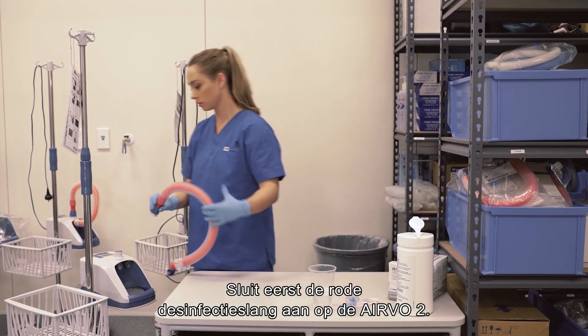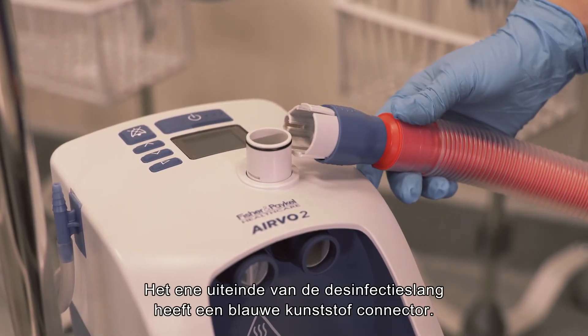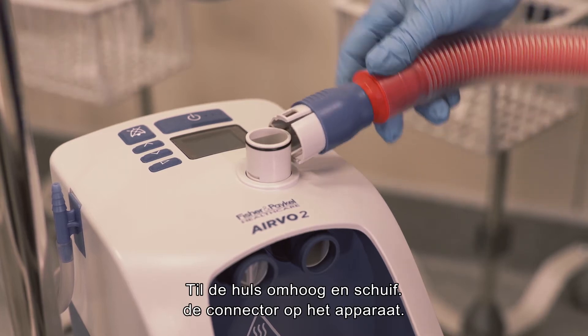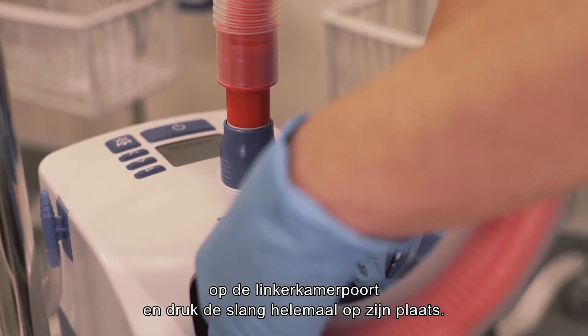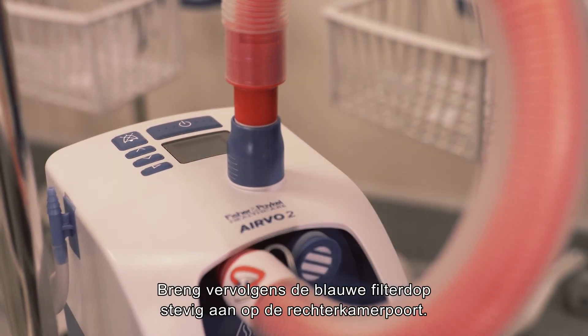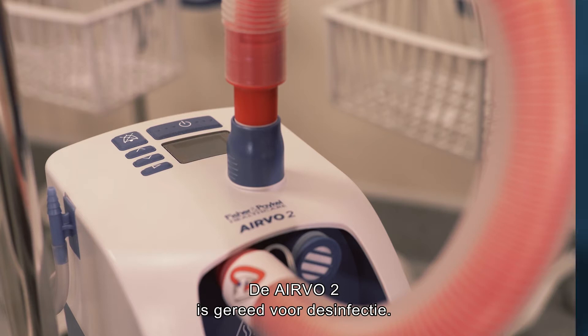First, connect the red disinfection tube to the AIRVO 2. One end of the disinfection tube has a blue plastic connector. Lift the sleeve and slide the connector onto the unit, then push the sleeve down to lock. Connect the red end of the disinfection tube to the left-hand chamber port and push fully into position. Then fix the blue filter cap securely onto the right chamber port. The AIRVO 2 is ready for disinfection.